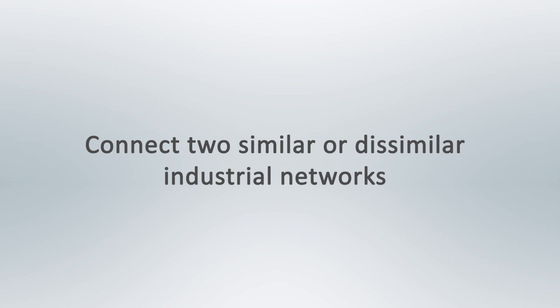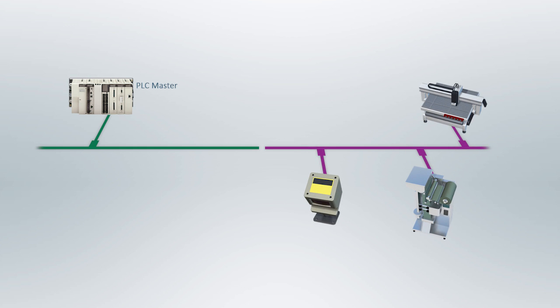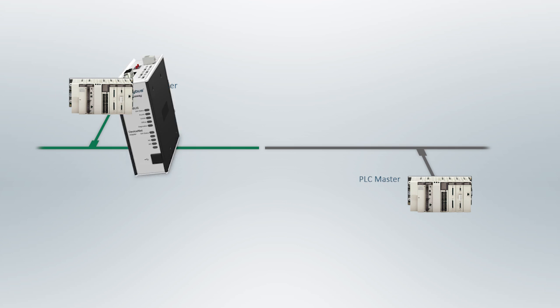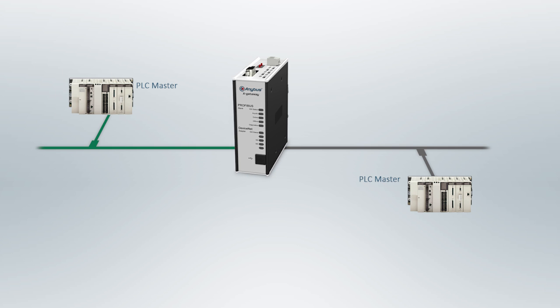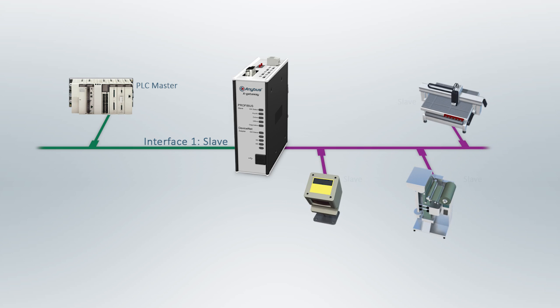If you want to connect two similar or dissimilar industrial networks, you first need to know if your network infrastructure has one PLC master which should communicate to several slaves, or if you have a PLC master on the other network as well. The reason for this is that if you have two PLCs, the gateway will be slave on both sides. If you only have one PLC, the gateway will be slave to the PLC and act as a master to the slaves on the subnetwork.